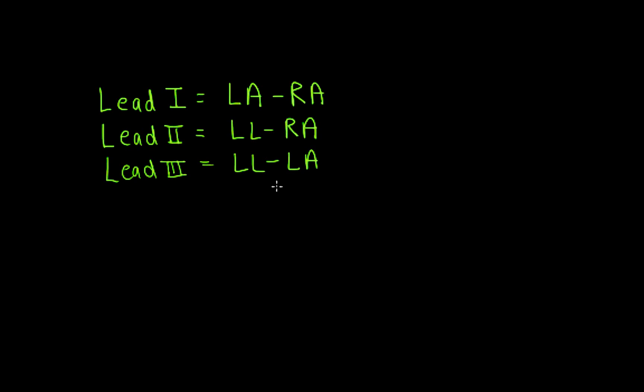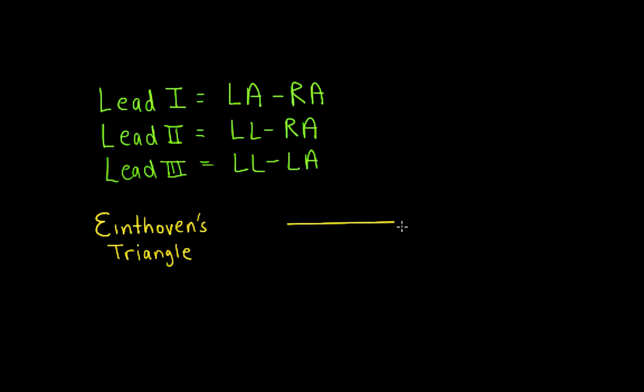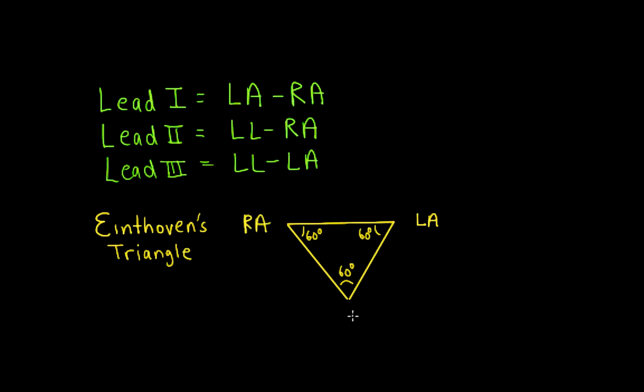Leads 1, 2, and 3 — the bipolar limb leads — can be represented schematically as an equilateral triangle. This is called Einthoven's Triangle, named after a Dutch physician who invented the electrocardiograph in the early 1900s. The heart sits in the center of this equilateral triangle, with 60 degrees at every angle. We have the left arm, the right arm, and the left leg electrode. The right leg electrode just functions as the electrical ground, so we leave that off this triangle.